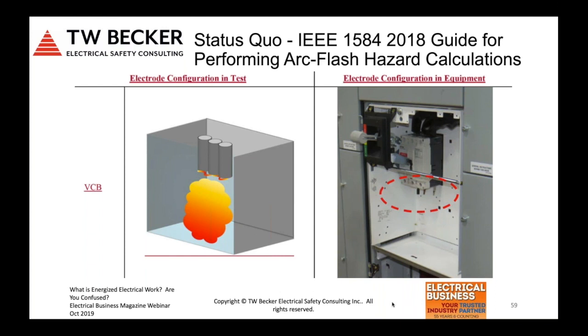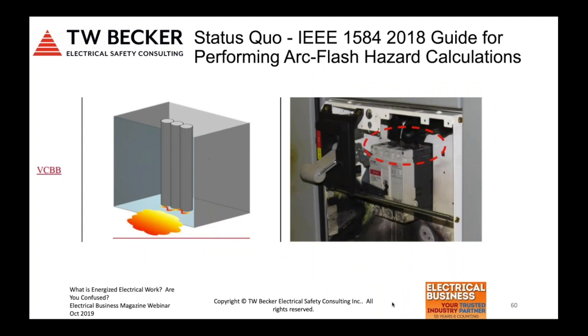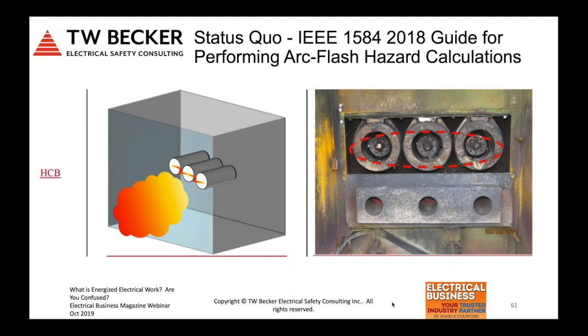Now, as far as the new IEEE 1584, previously there were only 2 electrode configurations. Now there are 5 box electrode configurations. So I'm putting focus on one of the key changes, that if you incorrectly determine the box and electrode configuration, the incident energy can go up. So you see an image, it's vertical conductor in a box. This was the actual test apparatus, and then they had vertical open air previously. So this was, again, a box electrode configuration tested for the 2002 formulas. This is one of the new ones though, vertical conductor box barrier. Horizontal conductor box, this is also a new box electrode configuration.